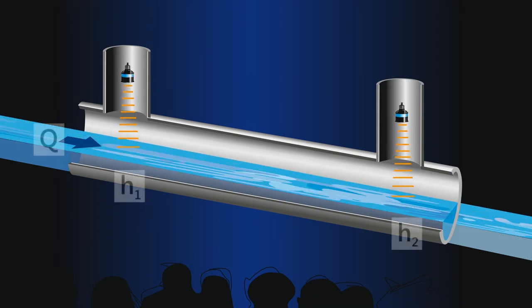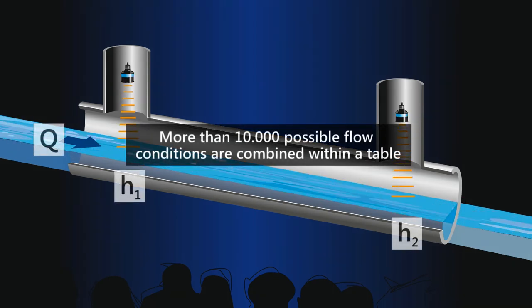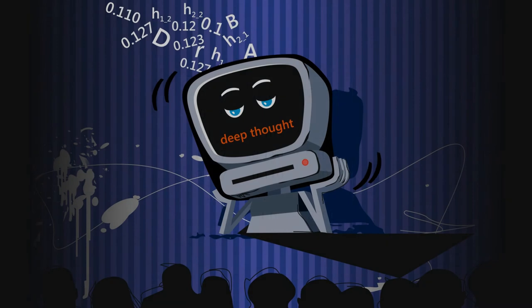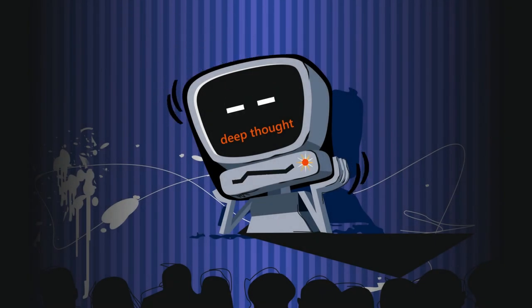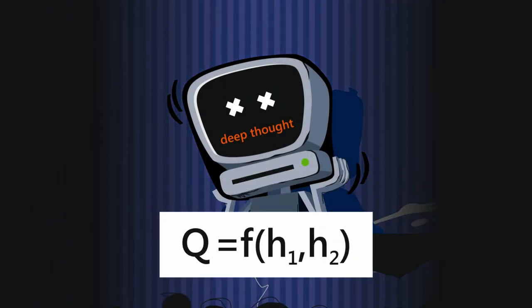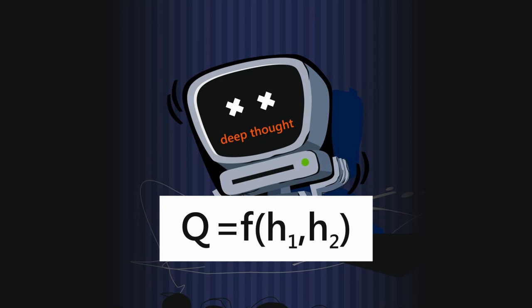After this, more than 10,000 possible flow conditions with two parallel levels are combined within a table. This table then is used to generate a specific equation, which makes it possible to accurately compute the flow rate based on both level readings.